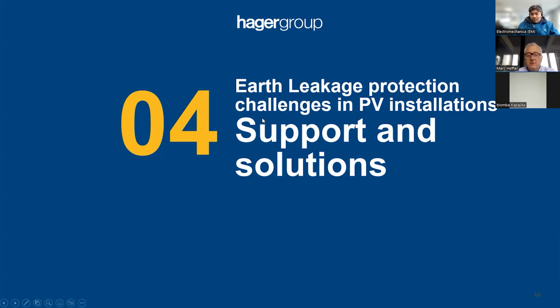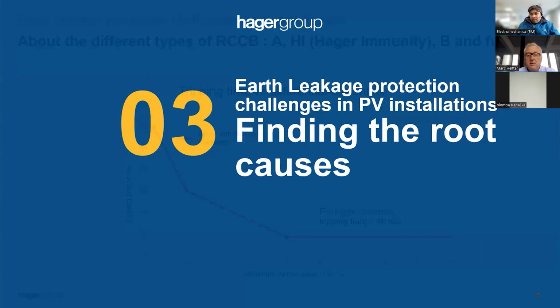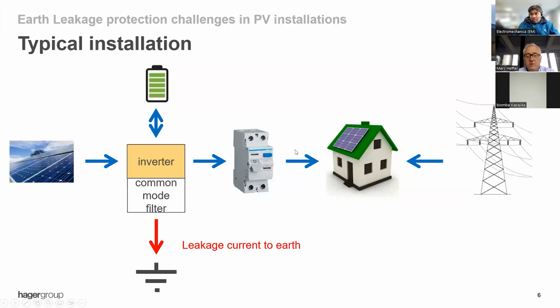So I just show you the position again. If you have this diagram, you have to put the filter here so that it will send the leakage to the earth, so that the RCCB won't see anything. The RCCB continues to see the current coming from the inverter, which is stable.